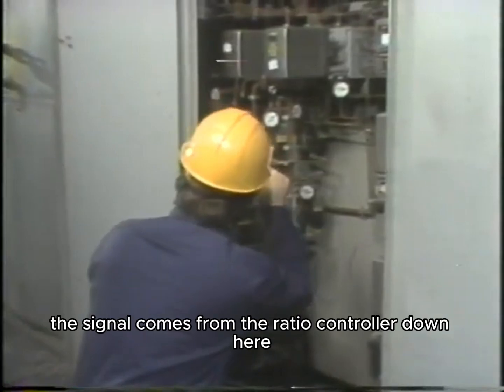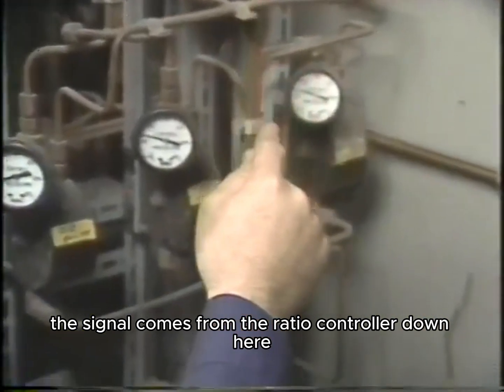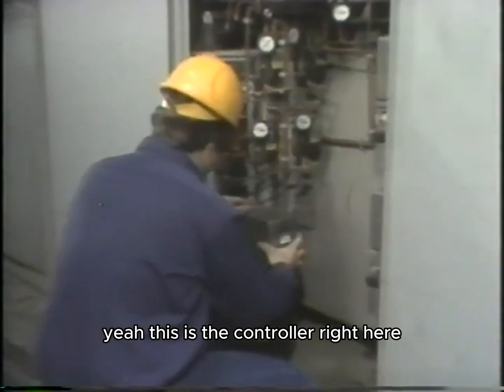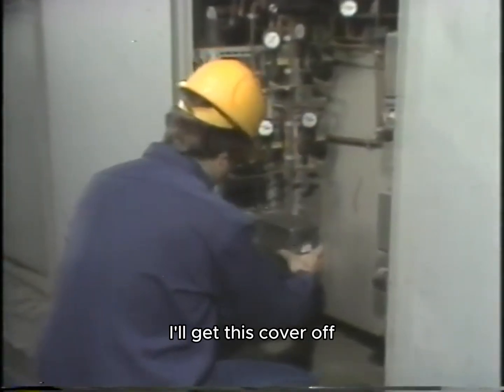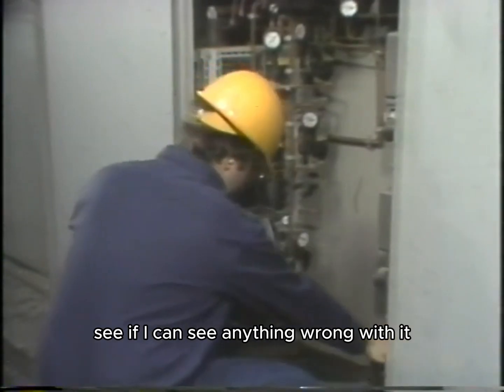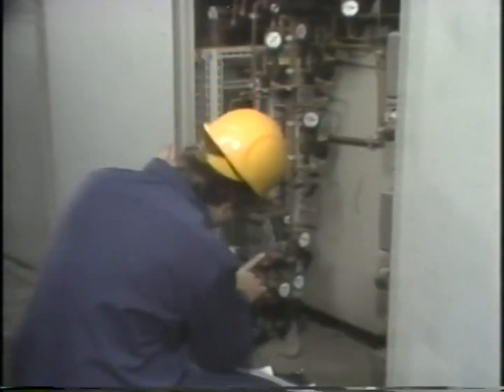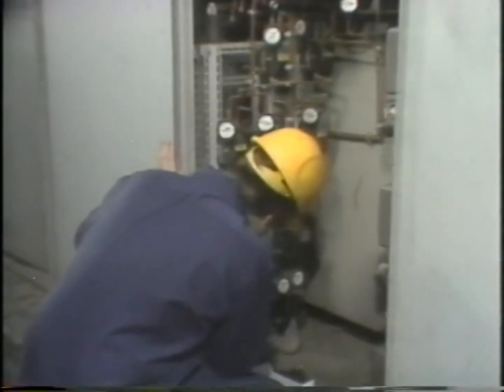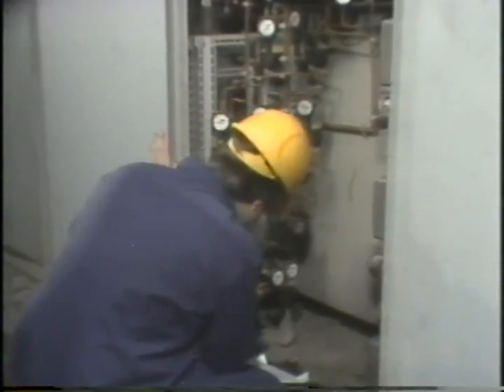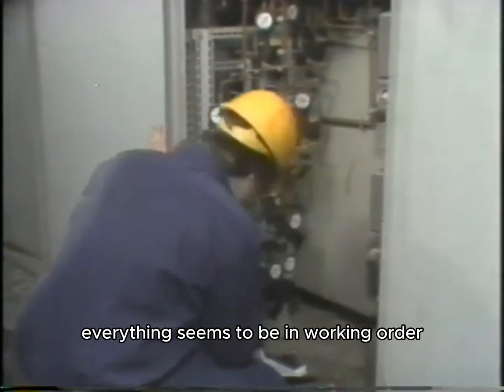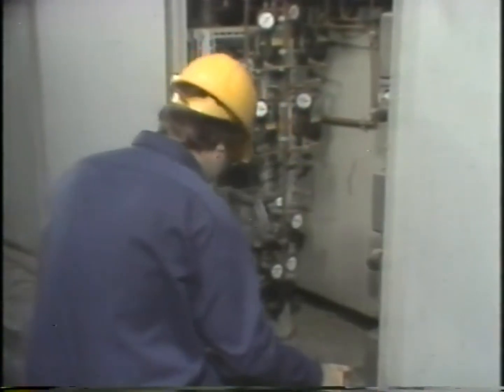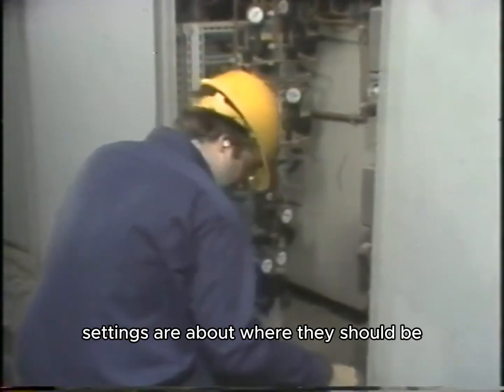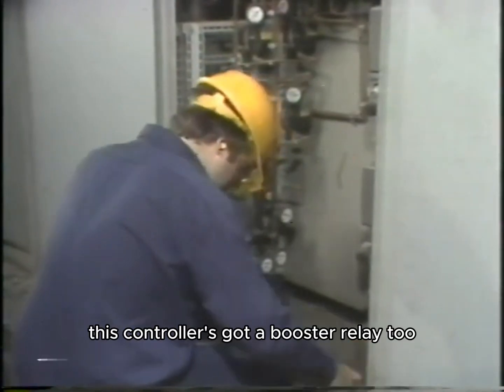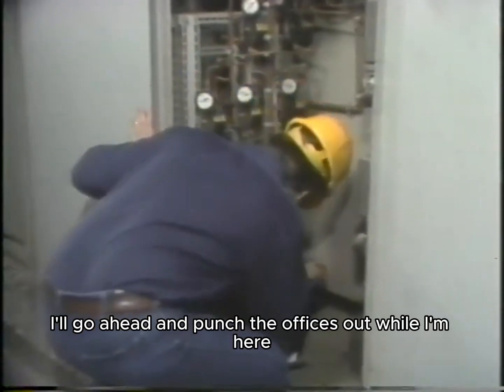Let's see, the signal comes from the ratio controller down here, down through here. Yeah, this is the controller right here. I'll get this cover off and take a look at this controller, see if I can see anything wrong with it. There. Everything seems to be in working order. The settings are about where they should be. This controller's got a booster relay too. I'll go ahead and punch the orifices out while I'm here.